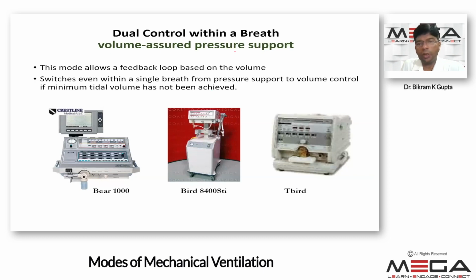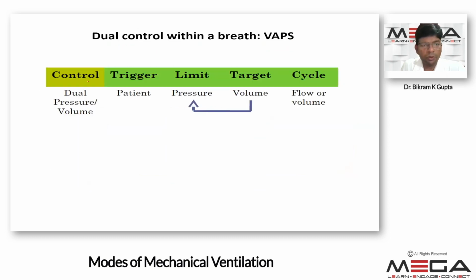So first one is the volume assured pressure support. This is based on a feedback loop, and the feedback loop depends on the volume. So it switches even within a single breath, intra breath, from pressure support to volume control if the target volume or minimum target volume has not been achieved. So the control here is either the pressure or the volume, because it changes intra breath from the pressure to the volume. Triggered by the patient, the limit is the pressure, and the target is the volume. If it is pressure control, then the cycling is the flow, and if it is volume control, then the cycling is the volume.